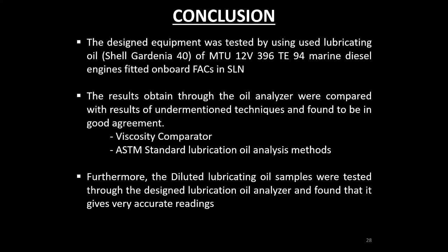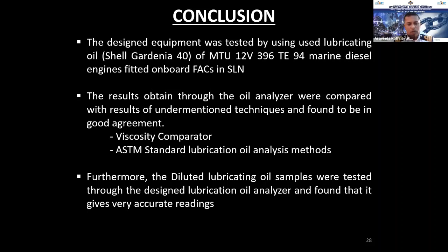I have checked a design equipment across testing Shell Gardenia 40 lubrication oil, and the obtained results were cross-examined with the available methods. Those are the viscosity comparator and also the ASTM standard methods. And also the equipment was further justified checking the diluted lubrication oil samples through the analyzer, and the reading was accurate.